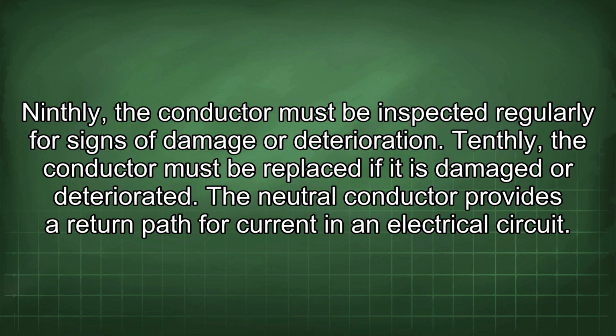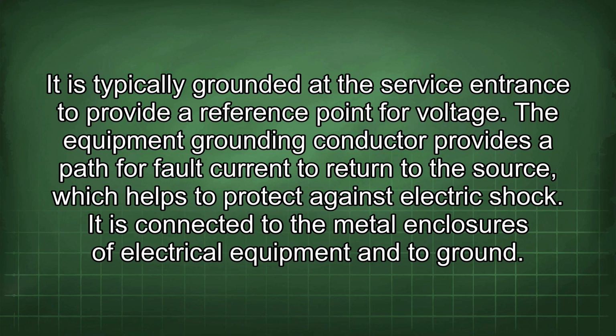The neutral conductor provides a return path for current in an electrical circuit. It is typically grounded at the service entrance to provide a reference point for voltage. The equipment grounding conductor provides a path for fault current to return to the source, which helps to protect against electric shock. It is connected to the metal enclosures of electrical equipment and to ground.